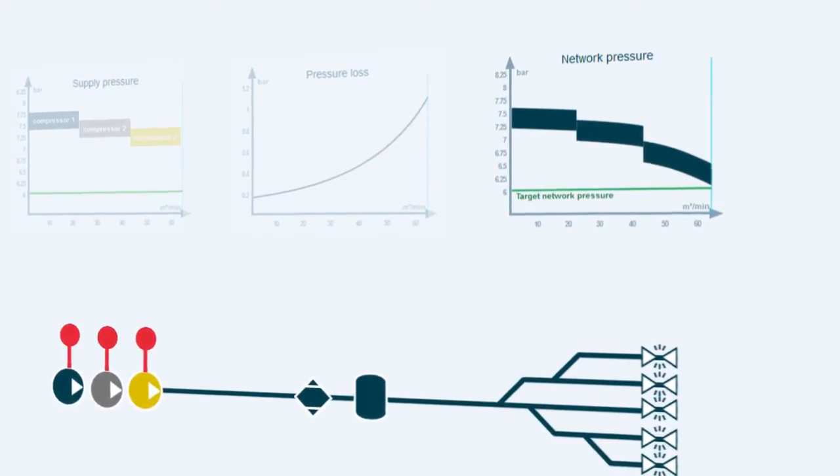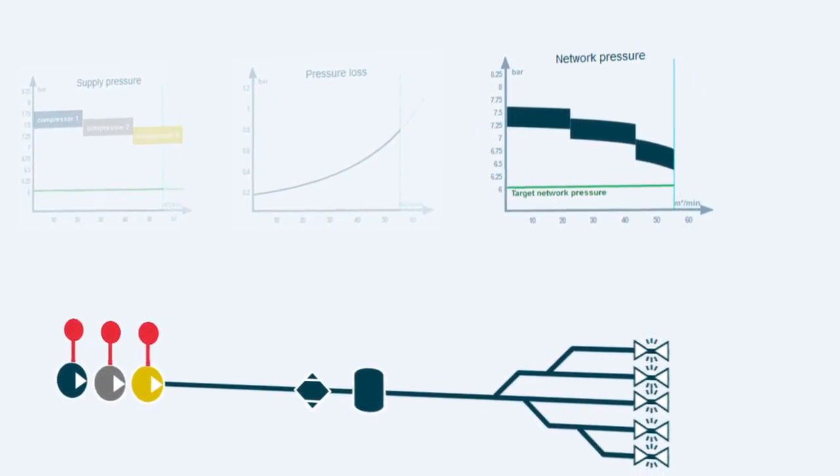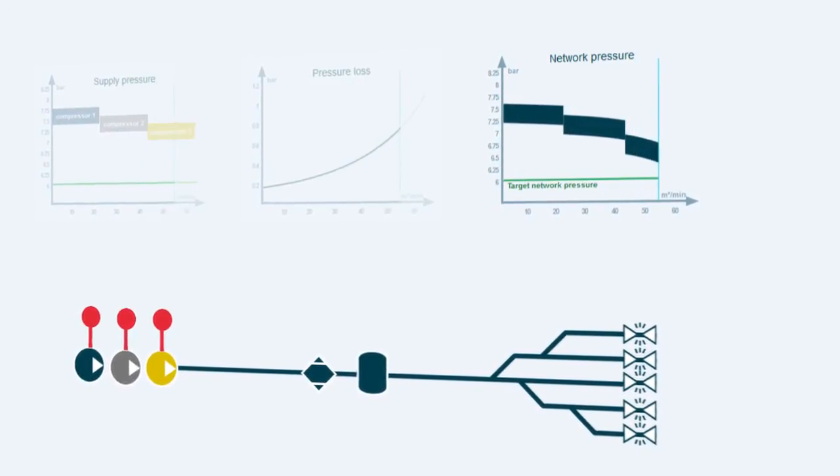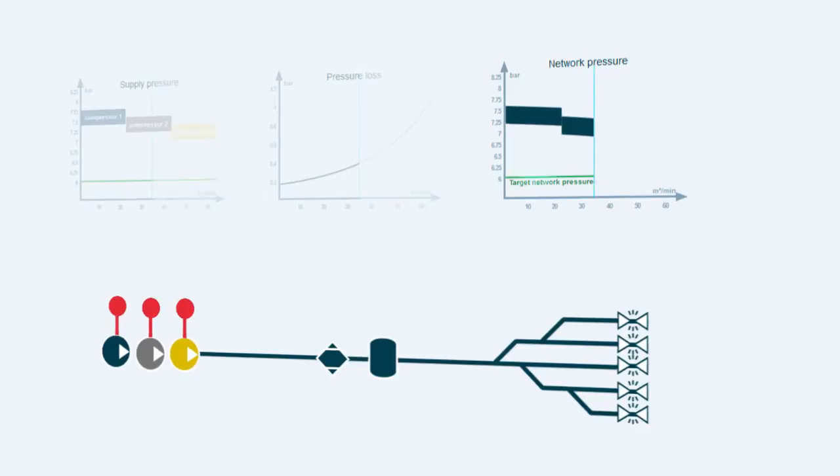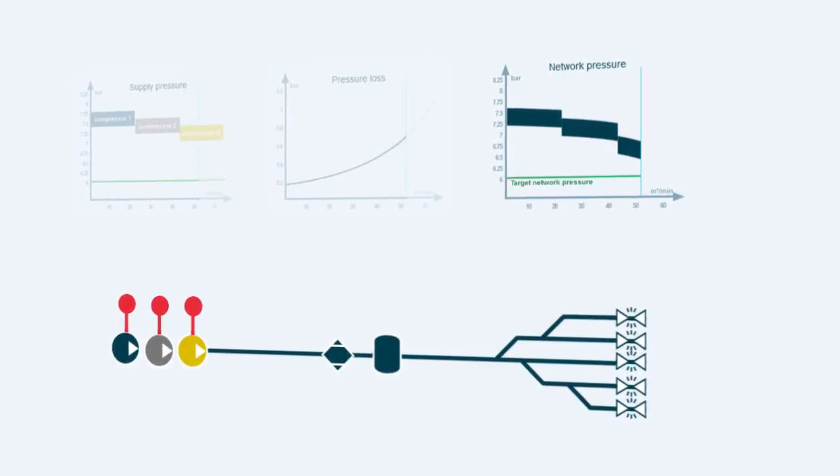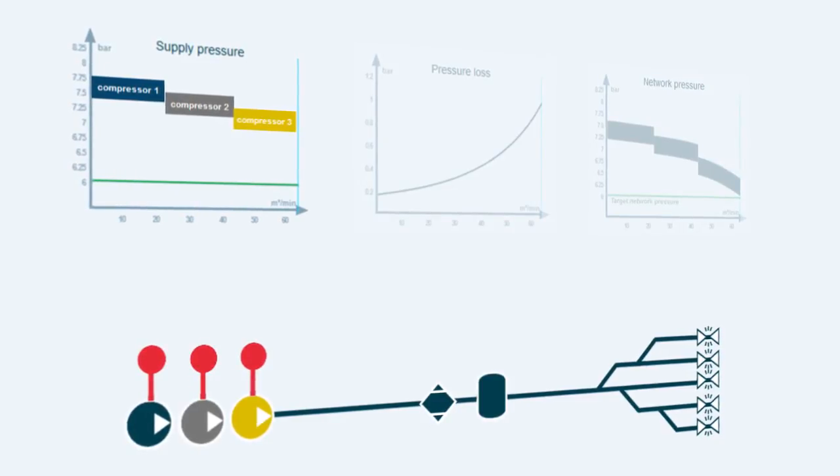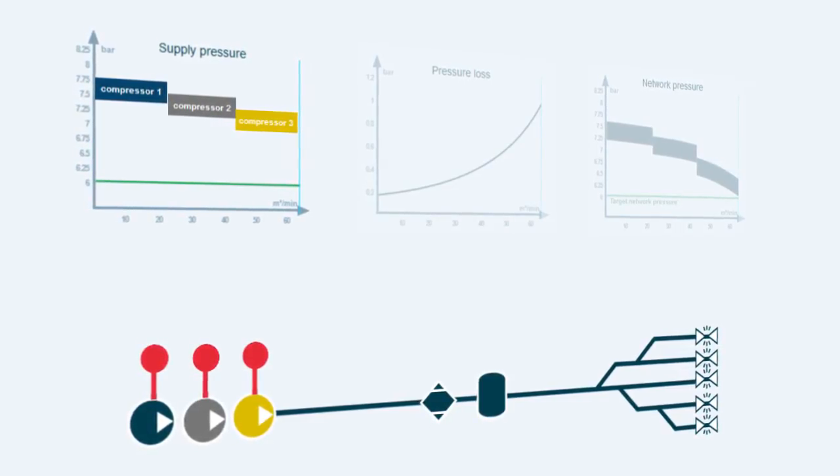The last graph shows the pressure level in the consumption point, the actual production. A compressed air system should be designed so that the system pressure maintains the minimum required pressure level in all situations. The green line in our example represents the minimum required pressure level. This diagram illustrates the compressor specific operation limit values.